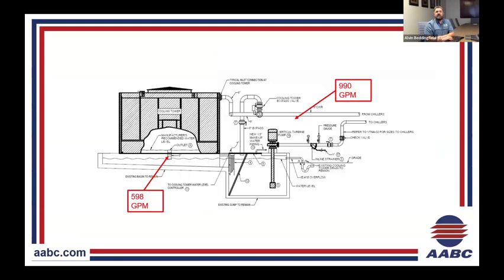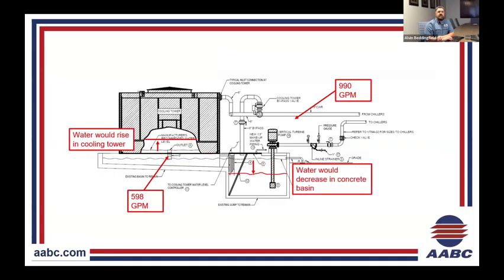So basically a snapshot of the tower. So basically we're coming in at 990 and we're only able to discharge 598. So kind of giving a snapshot of what we would see is basically the tower and the concrete sump would dramatically start to drop, and the basin of the cooling tower would increase, and then that's when it would just naturally roll over, because obviously we could not drain any more than the 598 out of that concrete basin. So that's kind of the situation that we're seeing with that one.